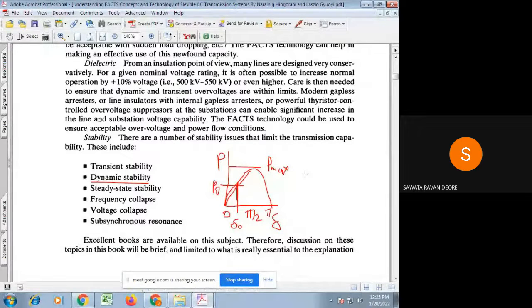Means as any load variation takes place, the governor will sense that and accordingly regulate the mechanical input to the generator. If there is any reactive power variation in the load, the automatic voltage regulator will sense the voltage and regulate the excitation of the synchronous machine. So if the effect of the automatic voltage regulator and the governor is considered while analyzing the steady state stability of the power system, then it is called dynamic stability.